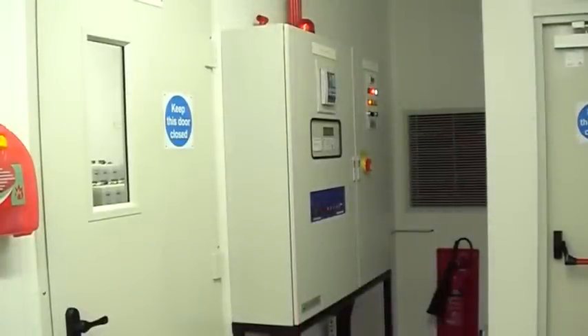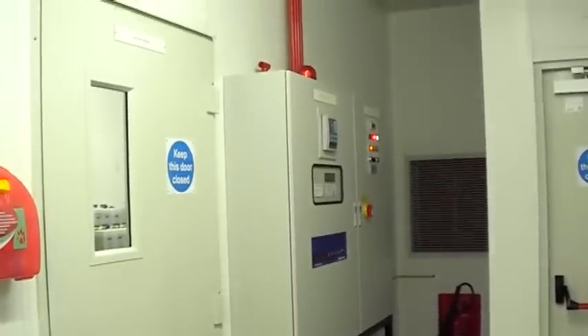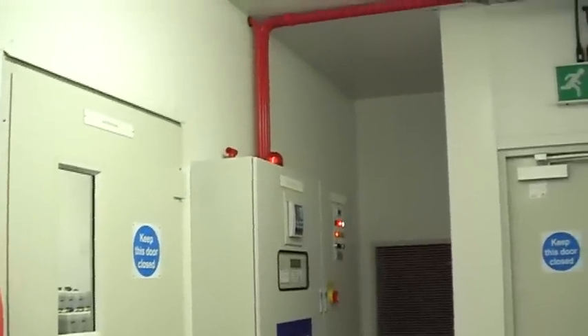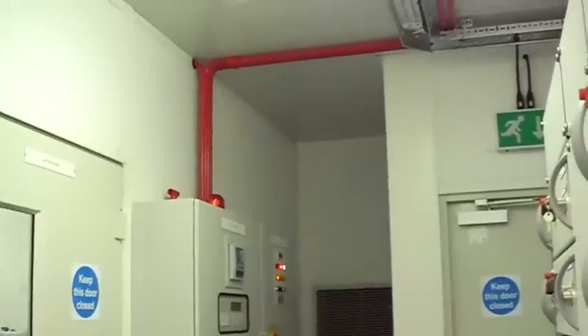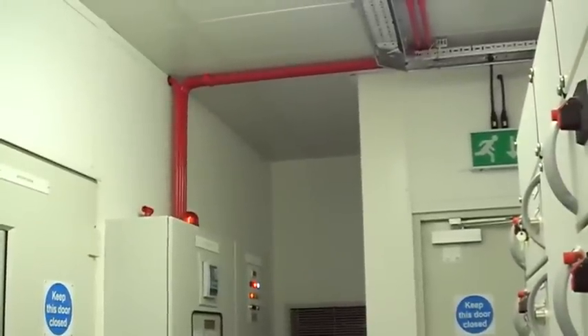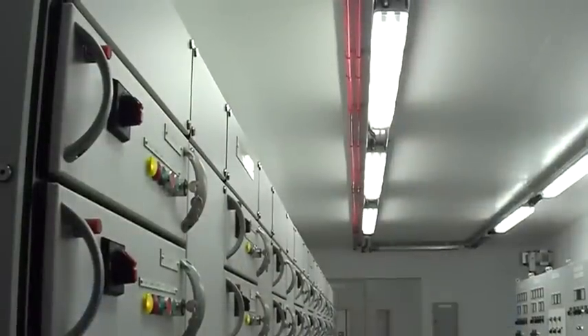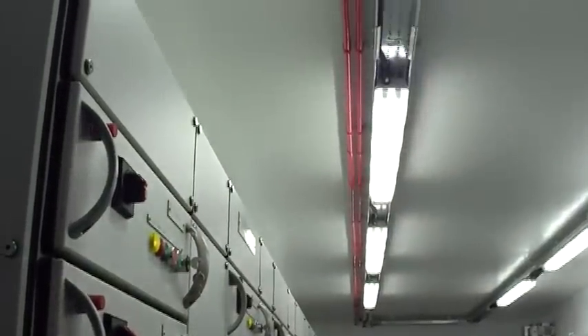Fire detection is carried out using VESDA. VESDA is an abbreviation for Very Early Smoke Detection Alarm and is an aspirator type detector. It comprises a vacuum pump connected to a series of sample pipes that run the entire length and width of the LER. Small holes are drilled in the sample pipes to provide very sensitive detection of fire over a vast area.